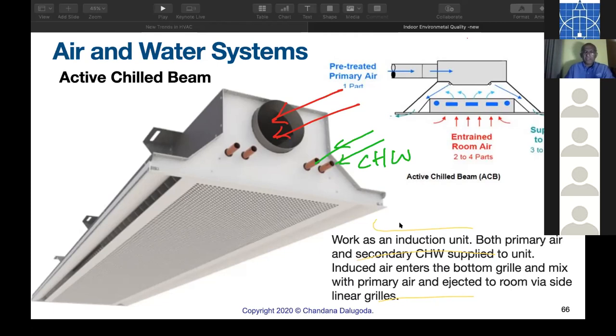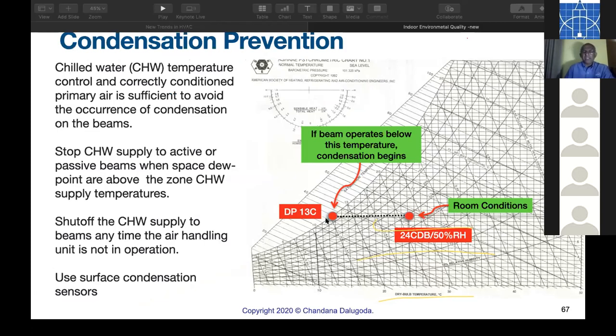Now, condensation prevention. See, the indoor dew point is 13C. So the coil has to be above 13. If it goes below, what happens? To understand this simply, we take a glass and put some ice cubes. Suddenly you notice you have condensation and you get water. Why? Say outdoor temperature is 32C dry bulb. Probably your surface is 10 degrees C. Dew point is 19, but your surface is very much below. So it is similar. If the surface goes below 13, there will be condensation. So you keep it above. So these are chilled beams, different types.